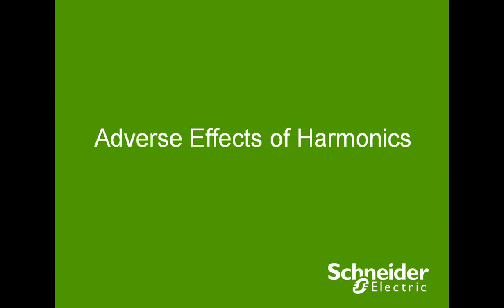All right. So here we come to the practical aspect of harmonics, the effects of harmonics. The first effect of harmonics will be heating. Heating will increase CO2 emission and reduce the network efficiency, and it will increase the energy cost for the consumer. So how exactly does heating affect the network with harmonics in the system.